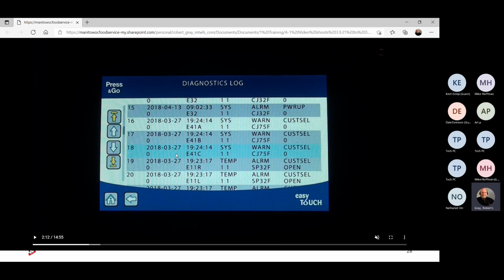So if I have a 41A, B, and C, I'm checking, first of all, power. Just use that as a rule. Checking incoming power to my contactor: do I have all 3 phases? Checking the output power of my contactor: do I have all 3 phases? If the answer is no, I have nothing on the output side of my contactor, then we're going to turn around and check one of those safety thermostat discs in the platen or the grill surface. Again, there's 5. One of them has opened up and it's not allowing the voltage to come back down to the coil of the contactor to close the contactor.